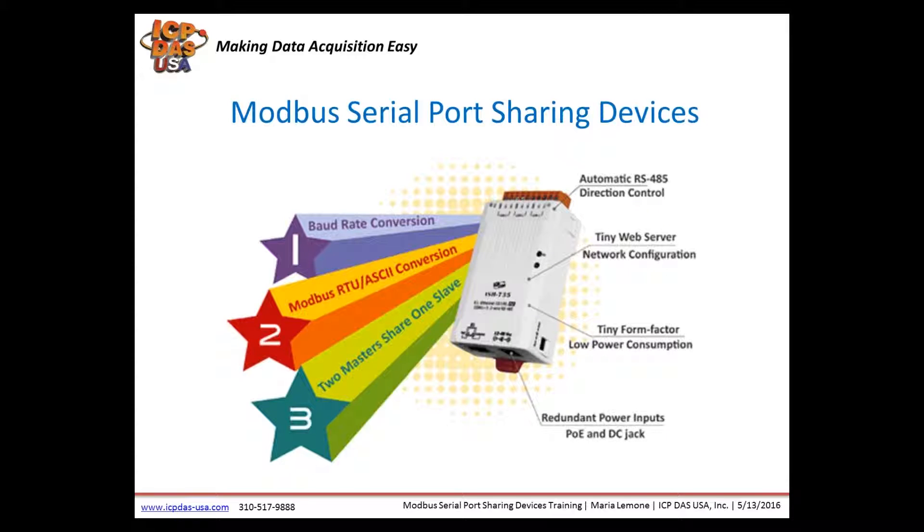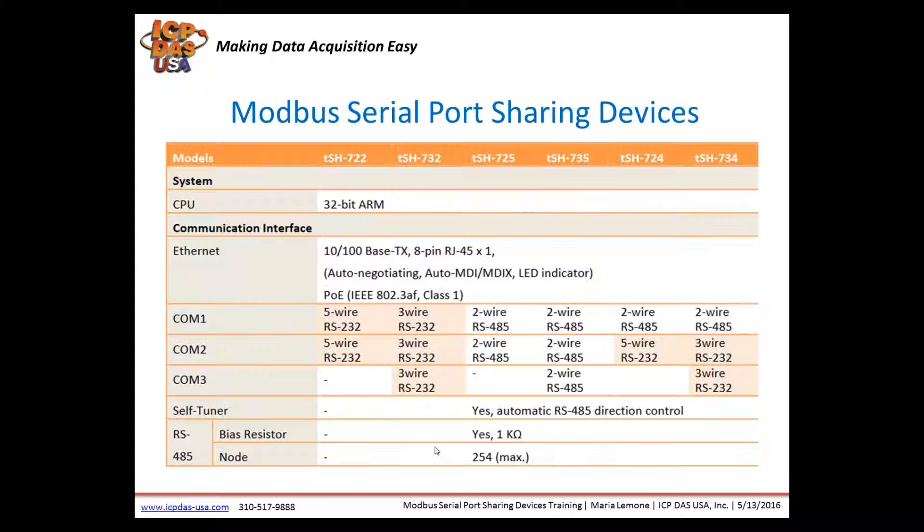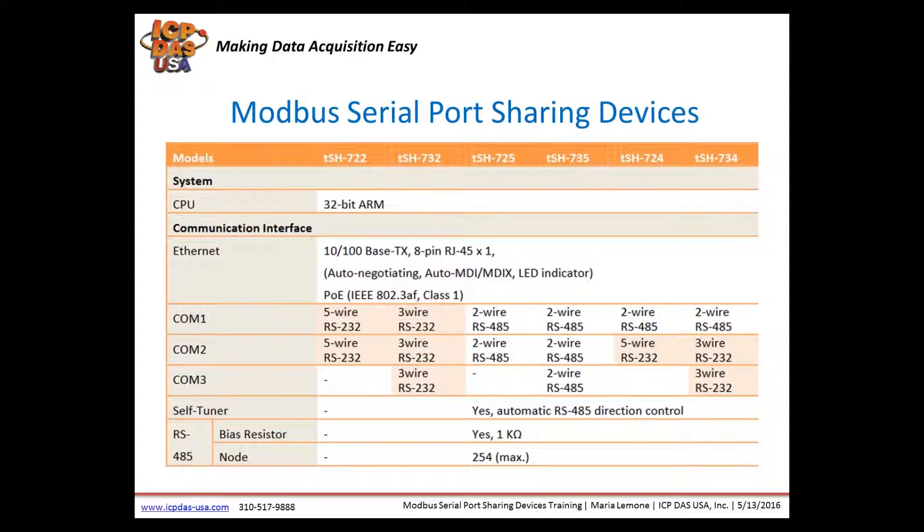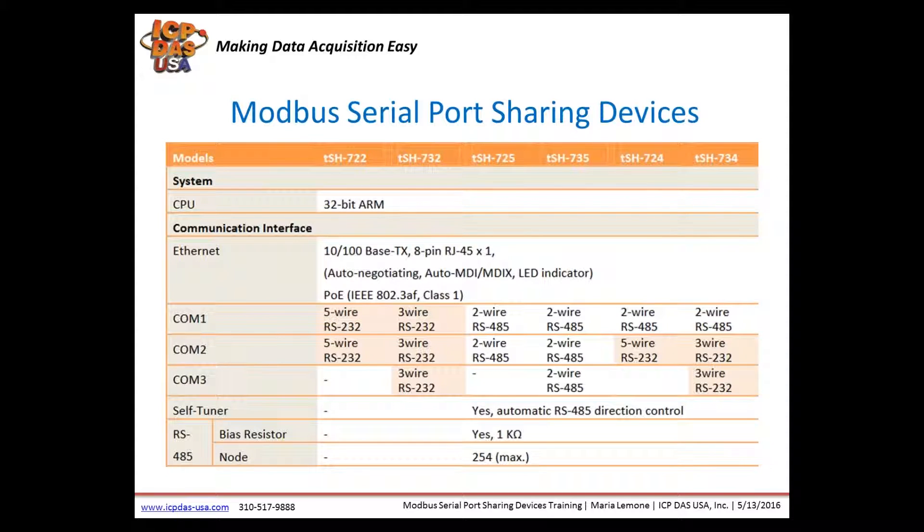Our new DIN rail mountable Modbus serial port sharing devices convert baud rates, convert Modbus RTU and ASCII protocols, and allow two masters to share one slave device. They automatically control the direction of the RS-485 bus, are configurable over a webpage through their web server, are very small in size, and have low power consumption. They can be powered over Ethernet by a PoE switch or powered by 12 to 48 VDC. They support operating temperatures between negative 25 Celsius and 75 Celsius.